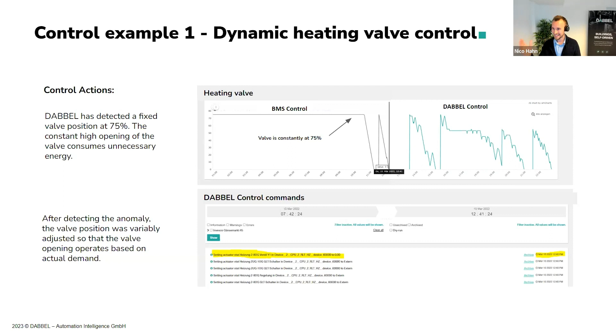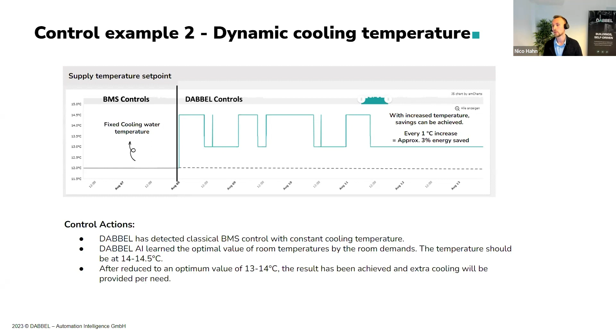The same mechanism can be applied for cooling valves. This is essentially the same. On most buildings, especially existing ones, we see very fixed static rules, simply engineered by a human being some years or decades ago. We transform this as well to the actual needs, with a forecast that calculates pretty accurately what the actual cooling need is right now, what the optimum value is, and we can execute that right in the back end of the software without having to call or notify the facility manager to change the setting. We apply it right away in the background.